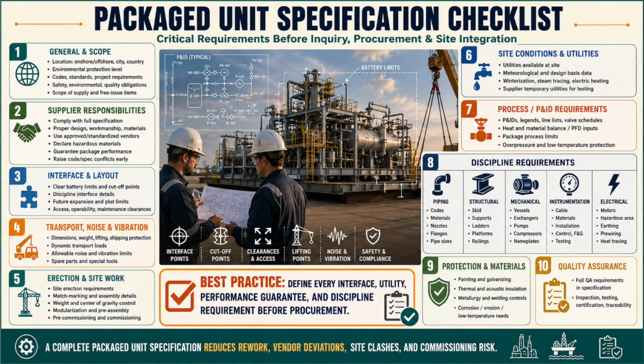Decide whether supplier standard nameplates are acceptable subject to approval or whether project and customer formats are mandatory. Nameplates affect asset identification, inspection, maintenance, and regulatory compliance throughout the equipment lifecycle. Instrumentation requirements are often where package integration succeeds or fails. Issue the applicable instrument cable, material, installation, automation, control, fire and gas, and testing requirements.